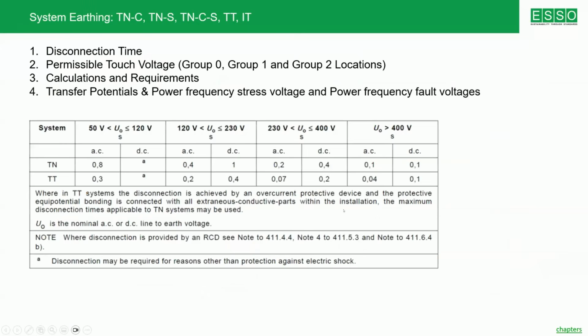which explain how to select a particular system for a particular application. Now, once you select a system earthing, the important subject which you should consider first is disconnection time. What is the maximum permitted time for tripping the supply? The standard recommendations you can see in this particular table. This table is from IS 732 or the National Electrical Code of India, which is actually the global requirement from IEC 60364-4-41 standard. The disconnection times used all over the world are the same. Depending upon the TN, TT, IT system, you have to decide. Depending upon the operating voltage, you should decide.